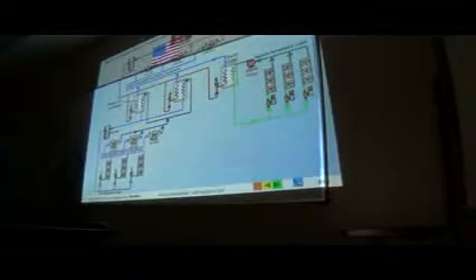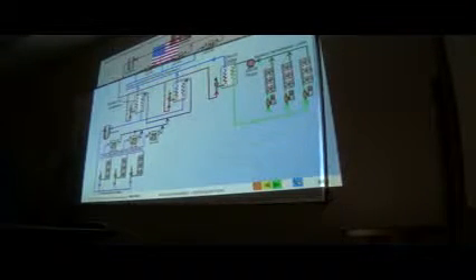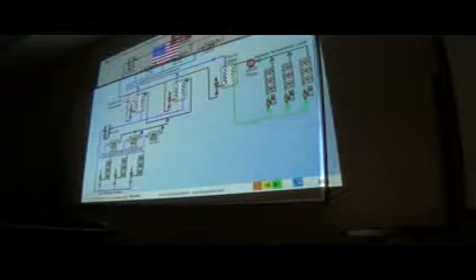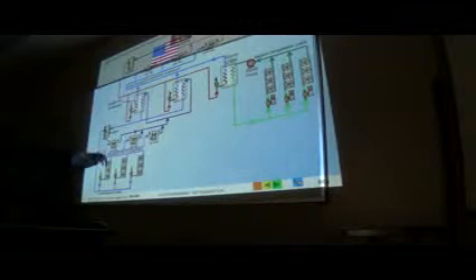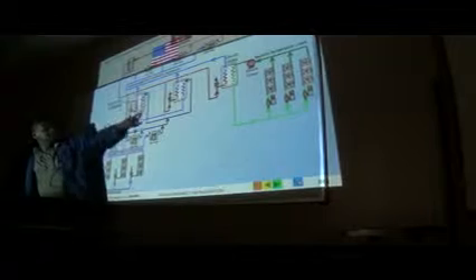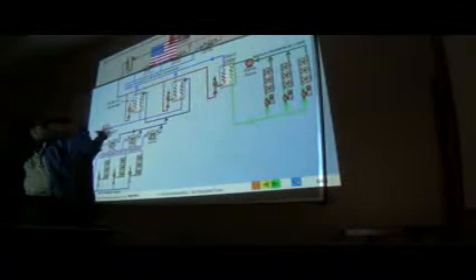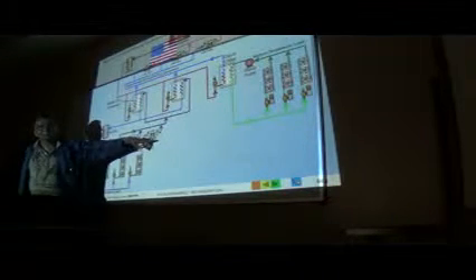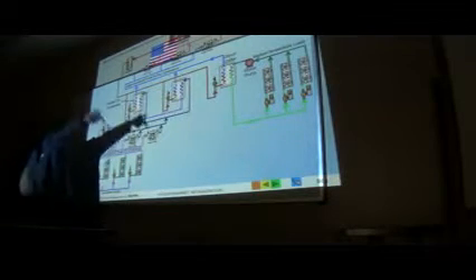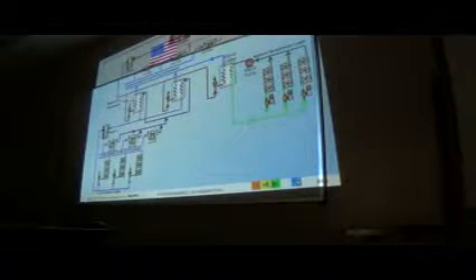System 1, a stage, cools down to medium temperature, say 35 degrees. That cools the condenser coil of my second stage, which takes me down to negative 50. Negative 50 then cools the condenser coil of my last stage, which takes me down to negative 100 or 125. That's how it works: the condenser of one system is cooled by the evaporator of another, and you keep going lower and lower, because ultimately you have to reduce that head pressure to get to that very low temperature.